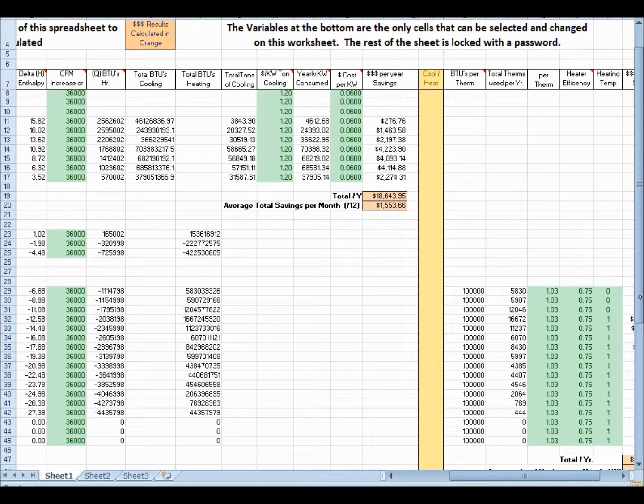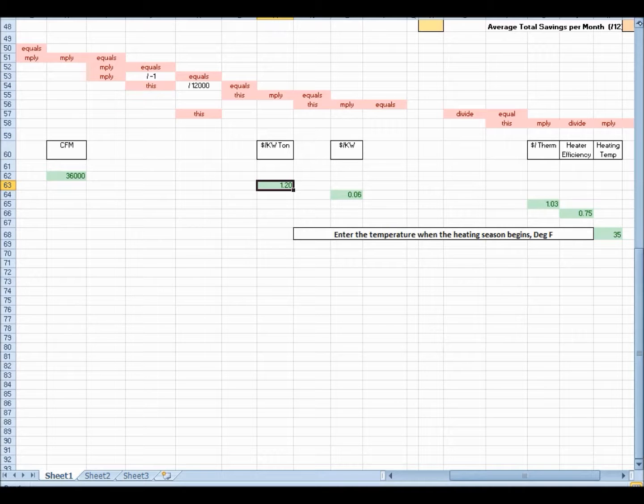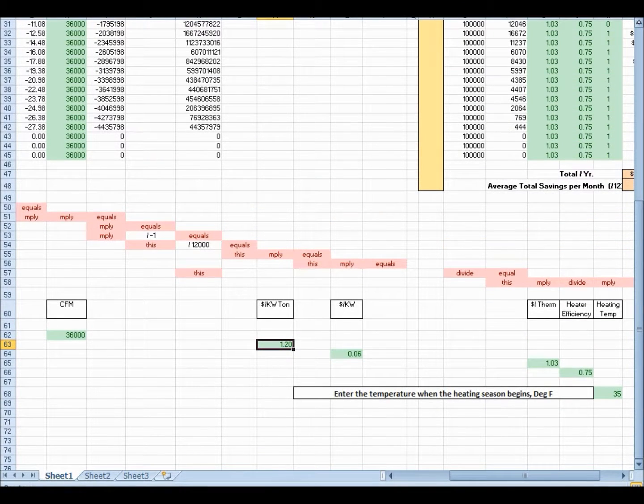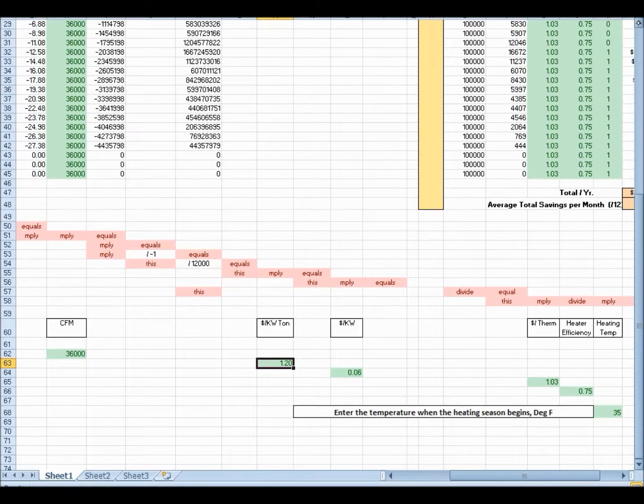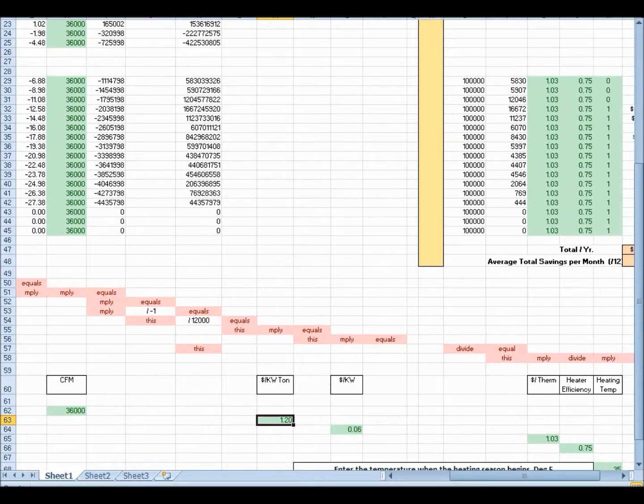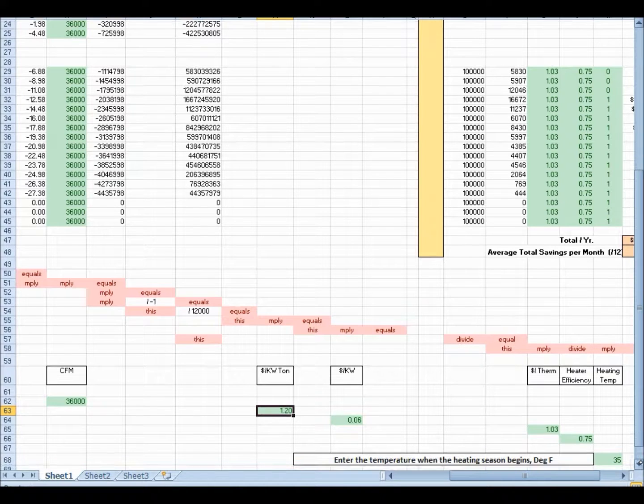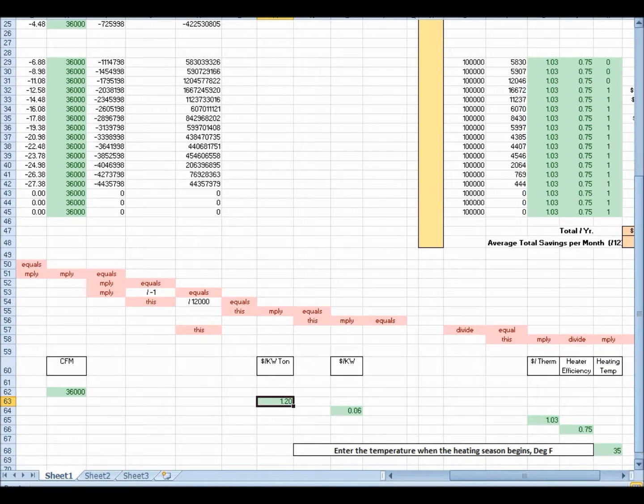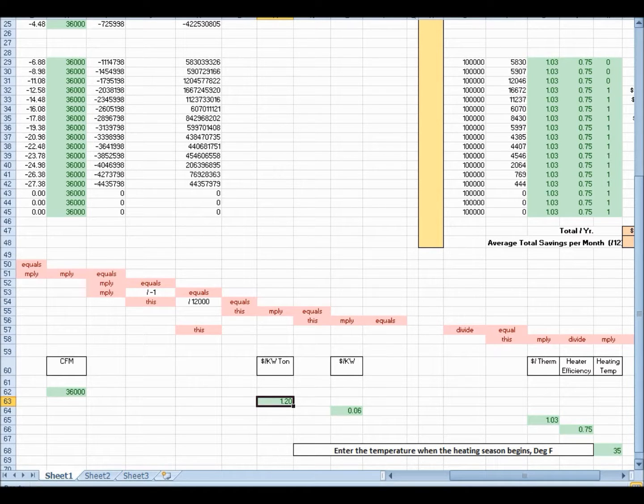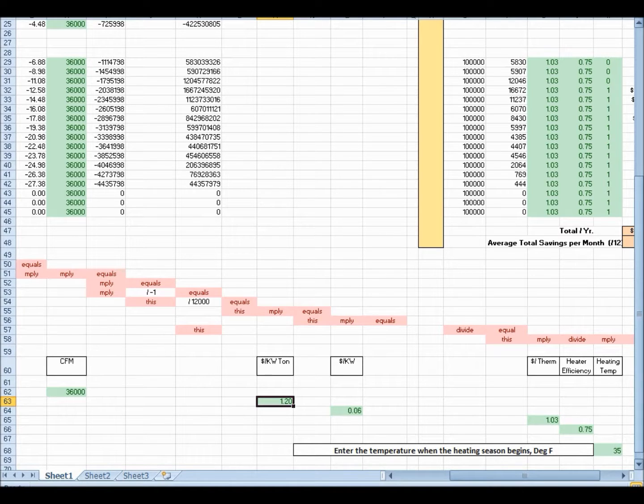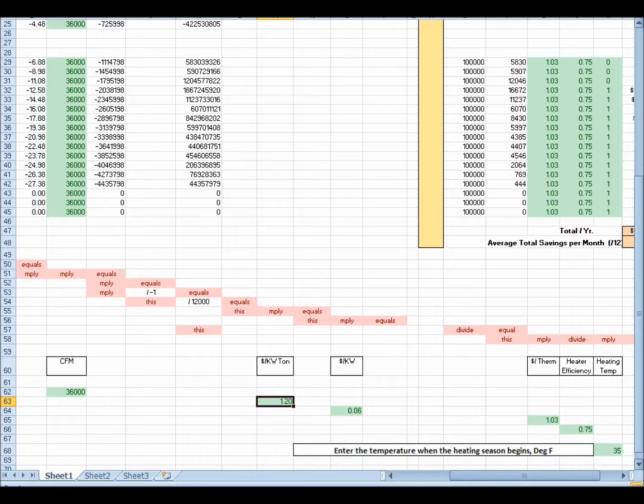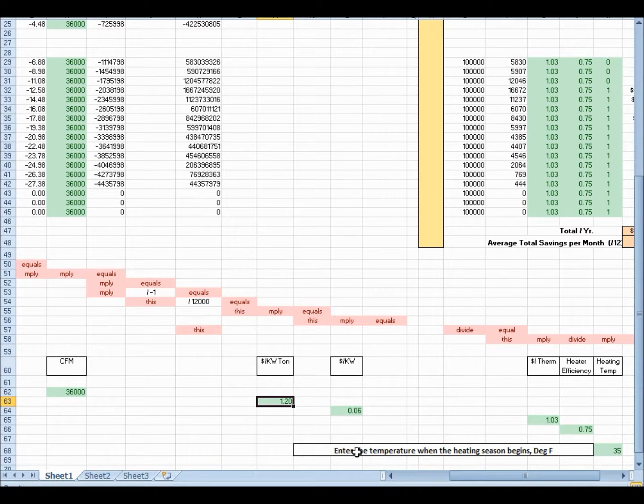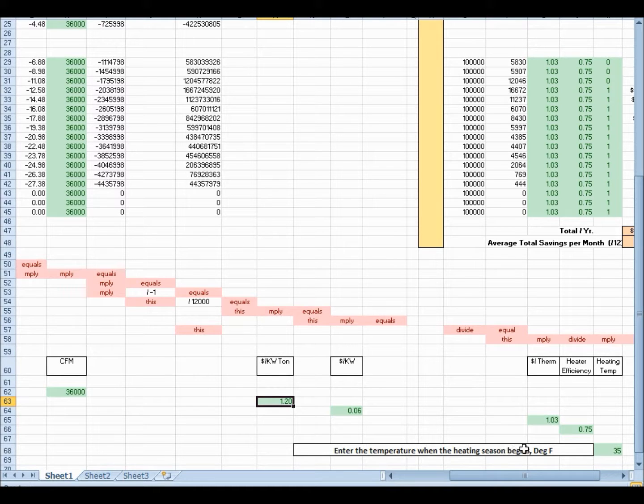Now, one of the other things that this calculator does on the heating side is take into account when you may start going into heating mode. Sometimes the load is great enough within the facility that you're in free cooling for a long time. So, you're taking advantage of that cold air outside, dumping it in the building, and actually cooling off the building. So, that varies. Over here in this column, as you go down here, you can see that we've got this 35 degrees. And this says, enter the temperature when the heating season begins. Let's say it's 35 degrees.